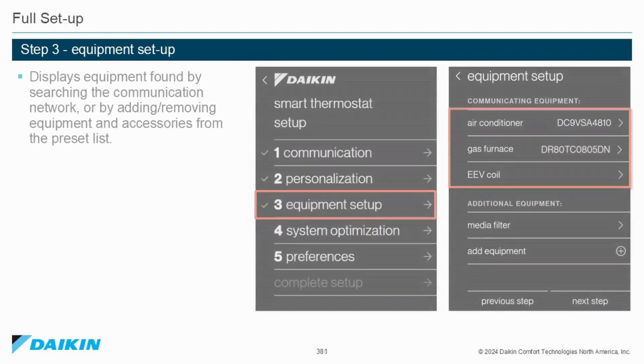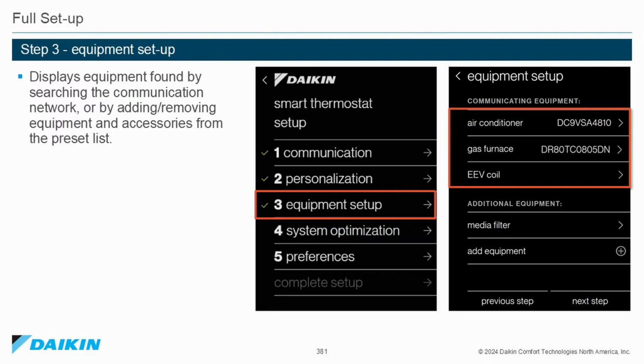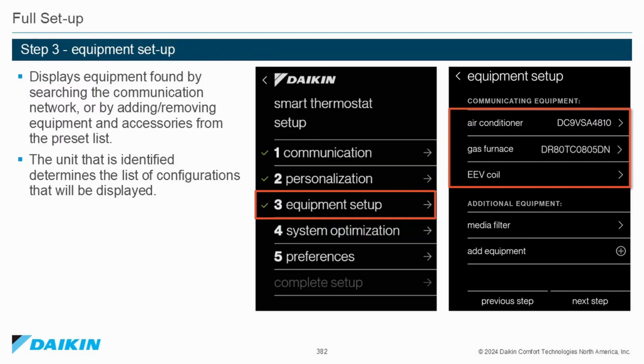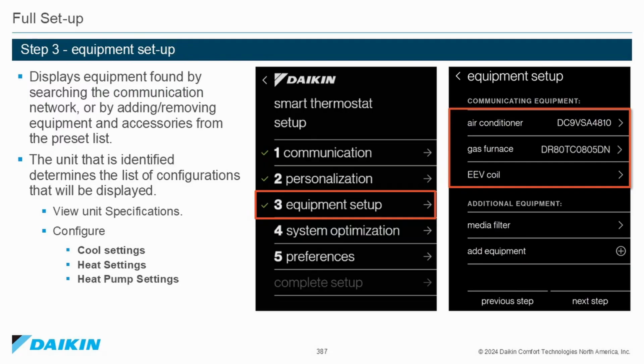Step 3. Equipment setup. This displays equipment found by searching the communication network or by adding or removing equipment and accessories from the preset list. The unit that is identified determines the list of configurations that will be displayed. View the unit specifications. Configure cool settings, heat settings, heat pump settings, humidifier relay, and heater kit.